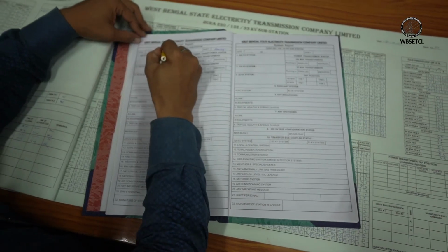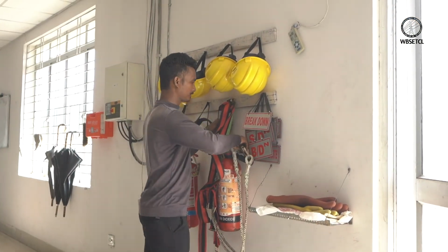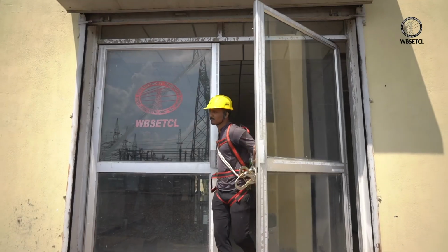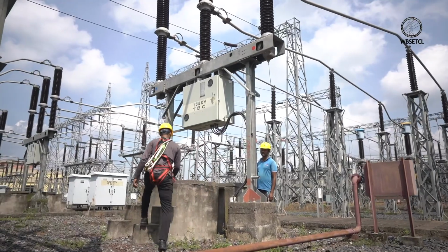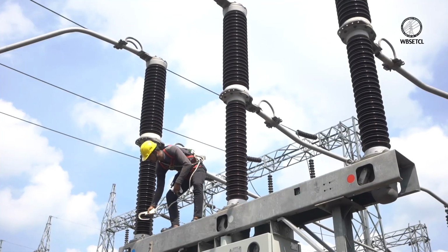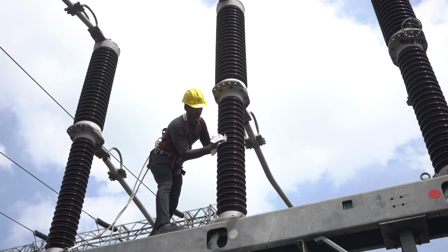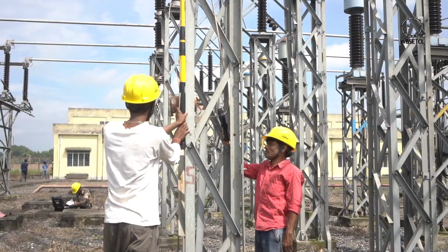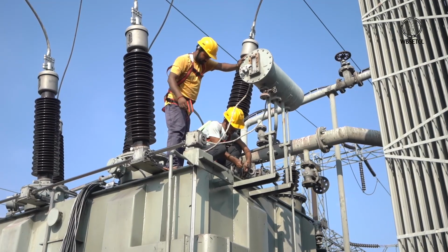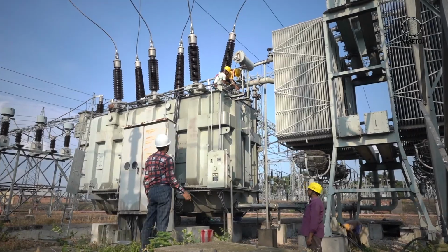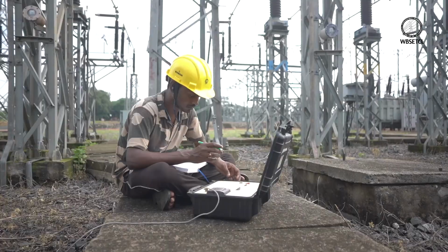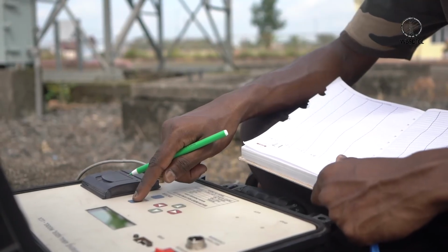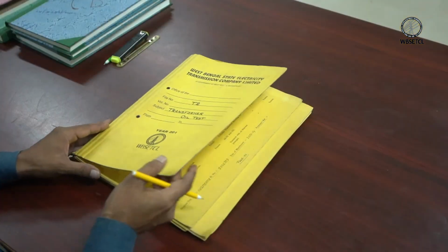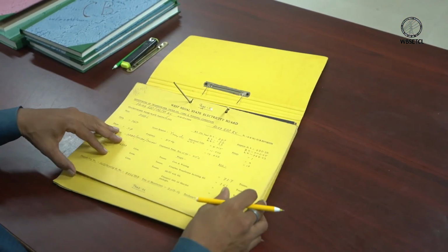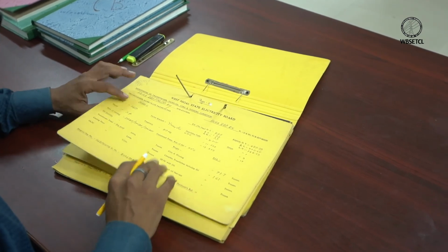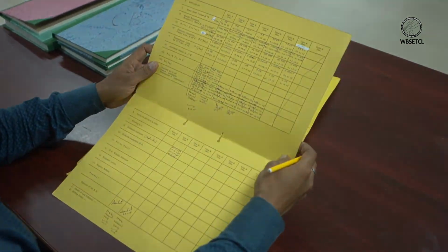in maintenance checklist registers. Periodic maintenance, including contact resistance measurement of CBs, timer and insulation testing through meggers of equipment, including checking and tightening of clamps and connectors of main bus, CT, circuit breaker, transformers and lightning arresters etc., are carried out regularly as per the maintenance schedule in order to achieve more availability or fewer breakdowns. Yellow cards are maintained for transformers, thereby monitoring the quality of transformer oil from time to time as per schedule.